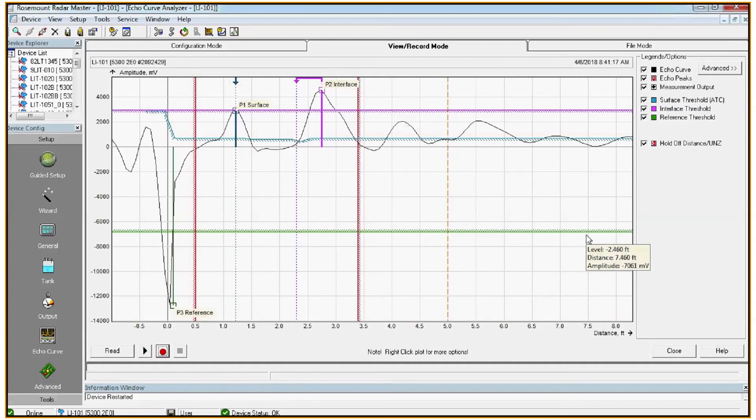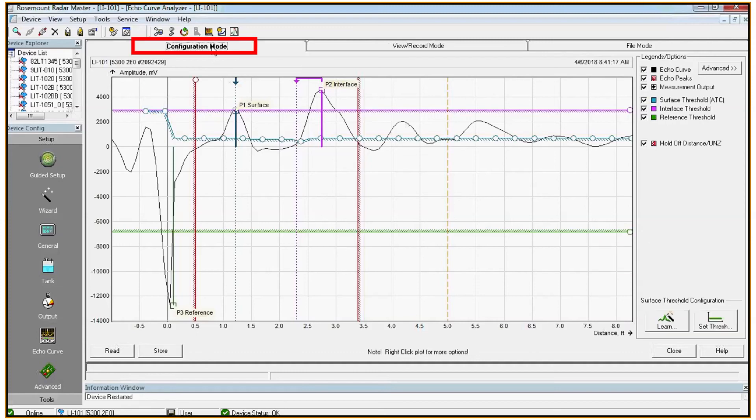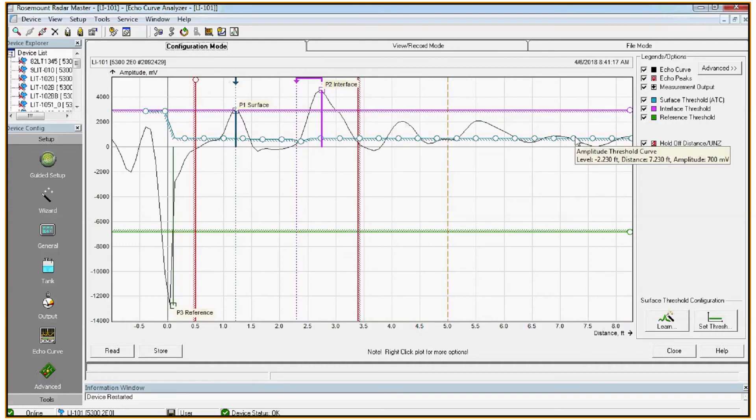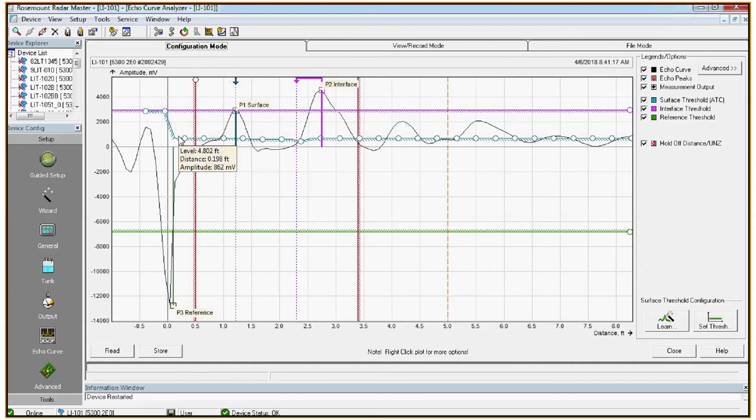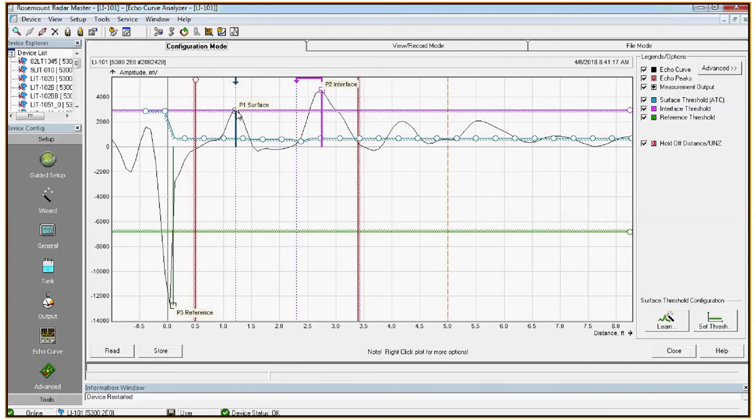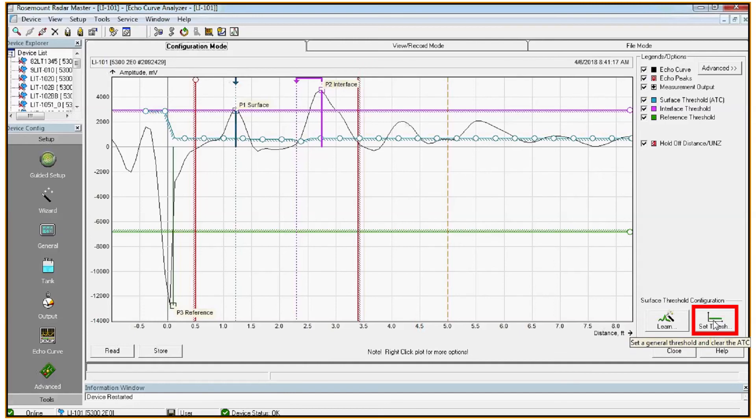If at commissioning it's not possible to see the tank empty, you can manually configure your filter settings or your threshold settings by going to the configuration mode. The blue horizontal line is the threshold for your top surface, so that is to say the peak of your top surface has to exceed the blue line to be identified as the surface echo. So to set the blue line at a set threshold, the general rule of thumb is to set it to about a third to half the amplitude of the surface peak. So in this case the P1 surface peak is at about 3000 millivolts, so we would set it at about 1500 millivolts. To do that, click on the set threshold button in the bottom right corner.